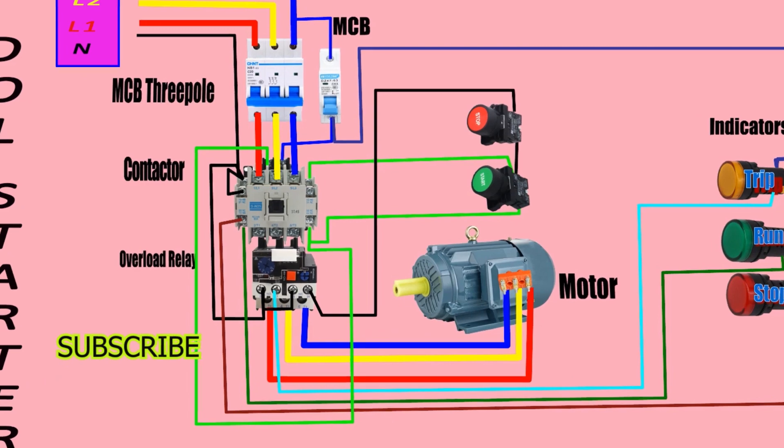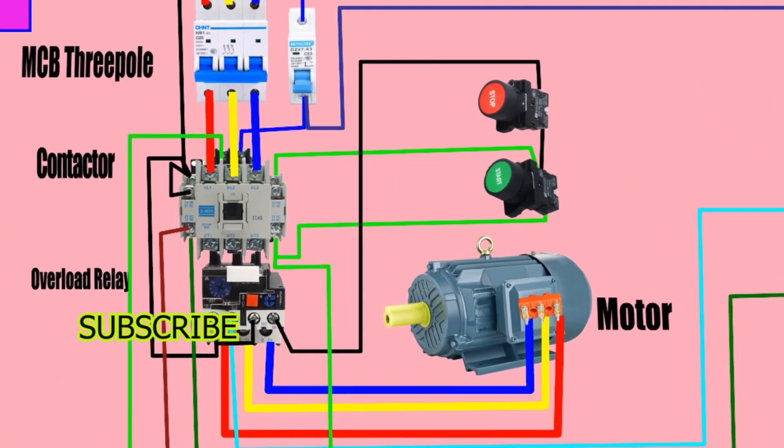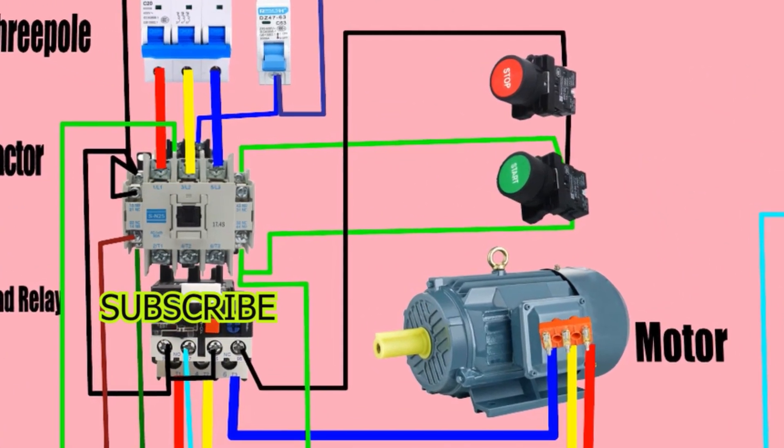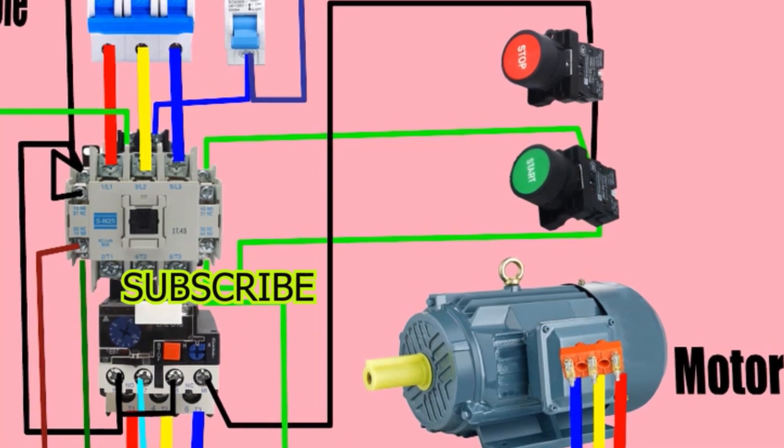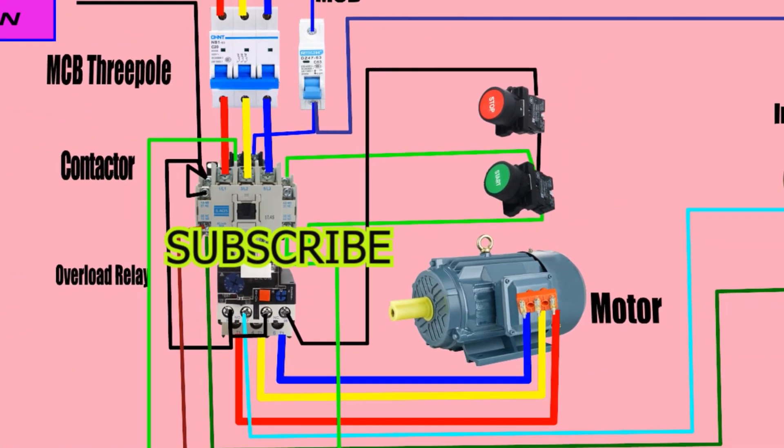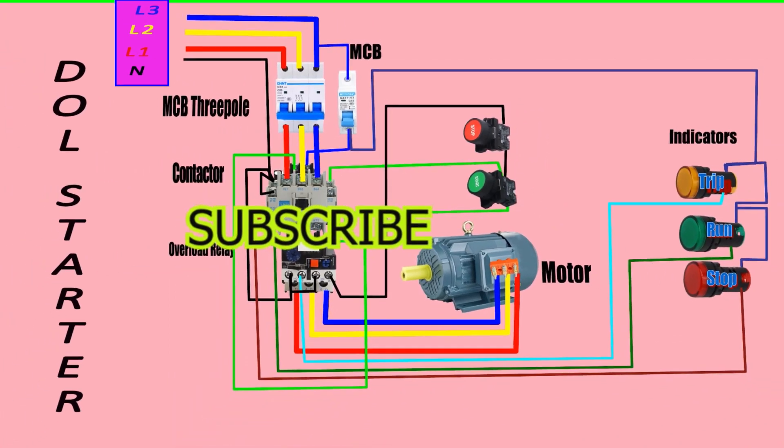When we press the start push button, the contactor closes, allowing the motor to be connected directly to the power supply. The overload relay monitors the current drawn by the motor and will trip the starter if the current exceeds a predetermined value.